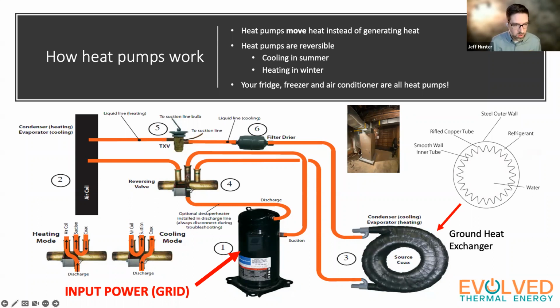We call that the source coax, and this one here also looks a little strange. They both do specific things in a heat pump. This reversing valve changes the direction of flow of the refrigerant — it's responsible for heating or cooling. When you go to your thermostat and switch it from heat to cool, all that thermostat is doing is sending a small voltage down to this box and shifting this valve one way or another, telling the refrigerant where to go. That refrigerant is responsible for the heating or cooling in our home.